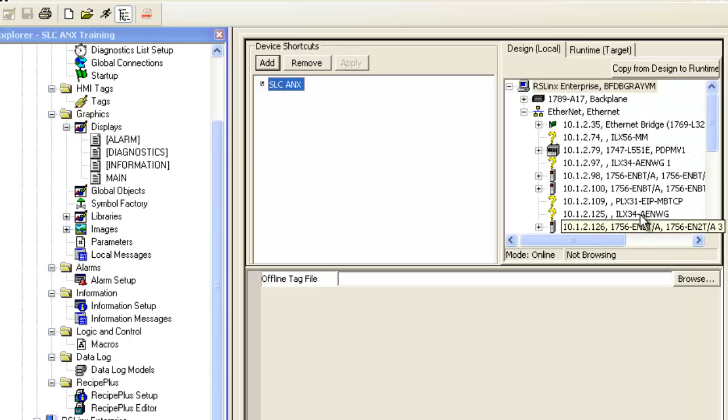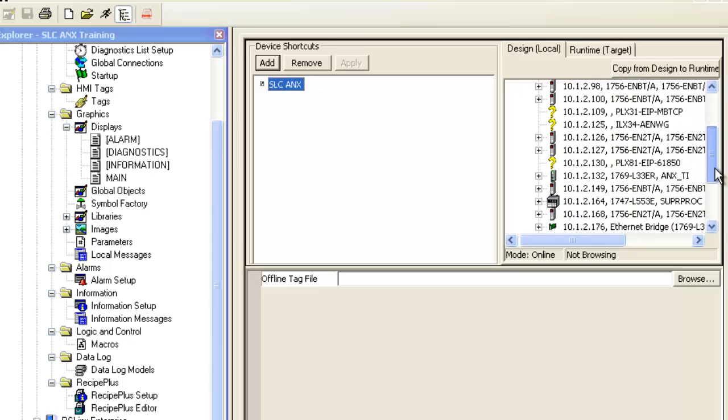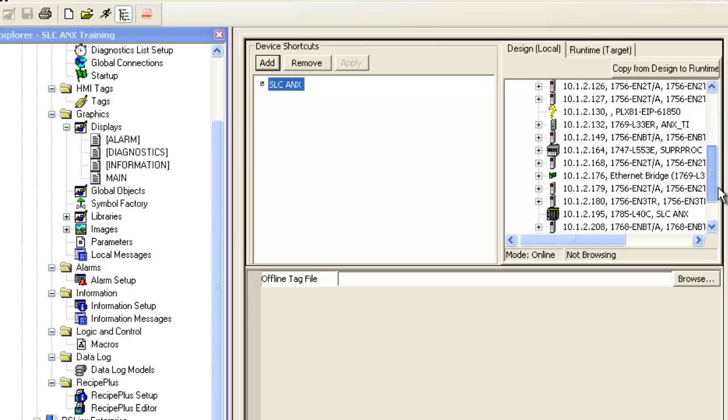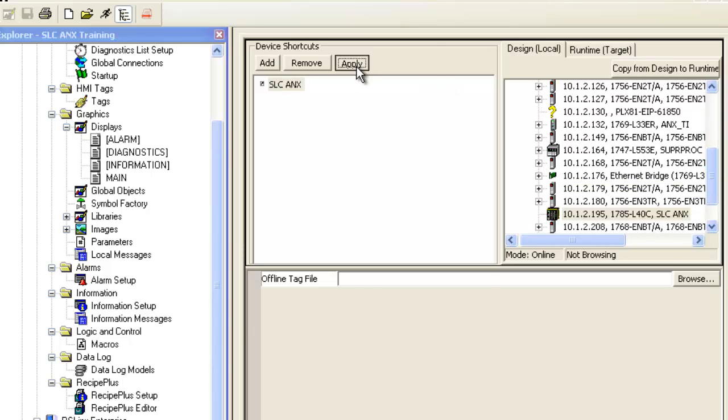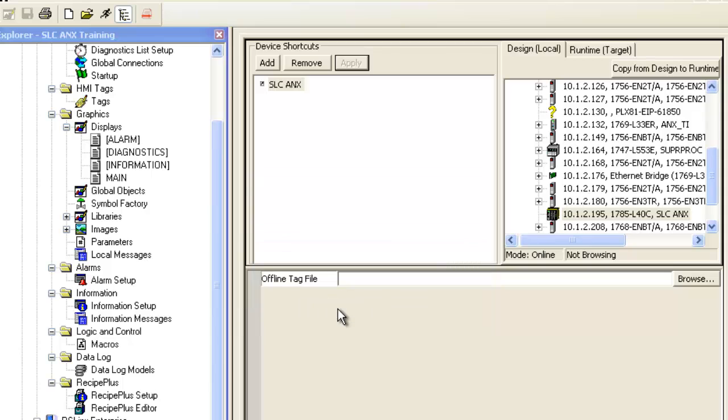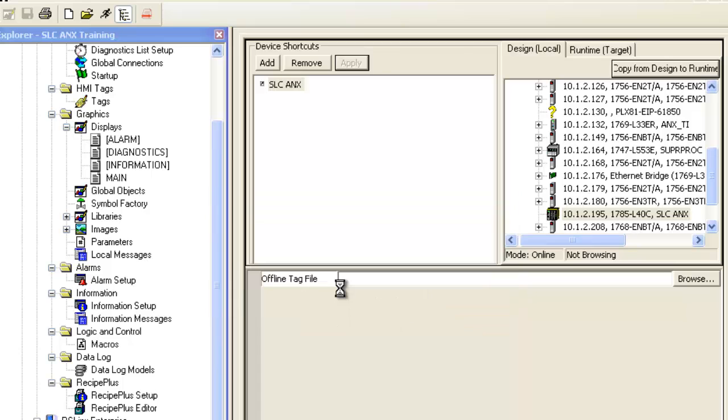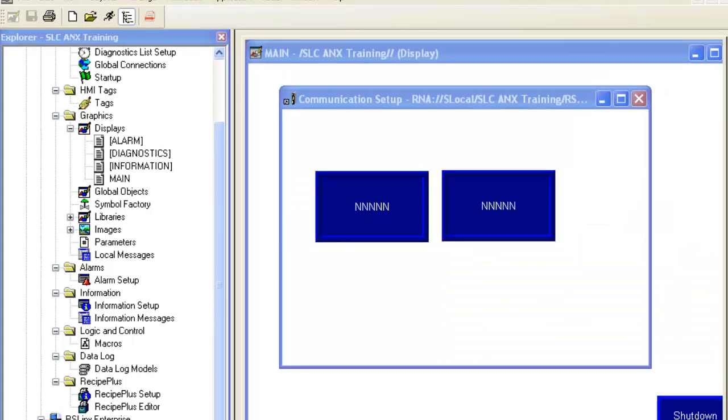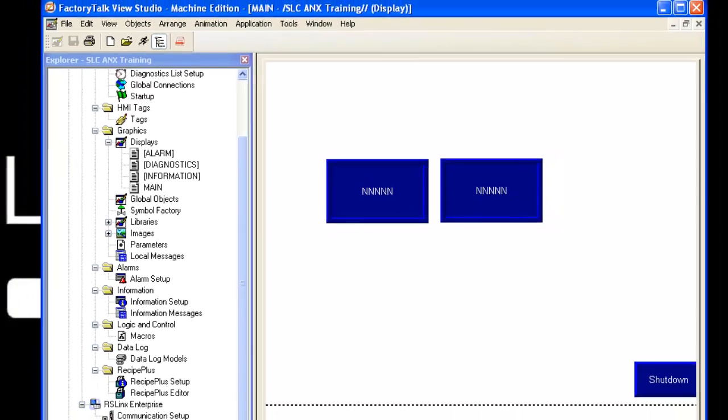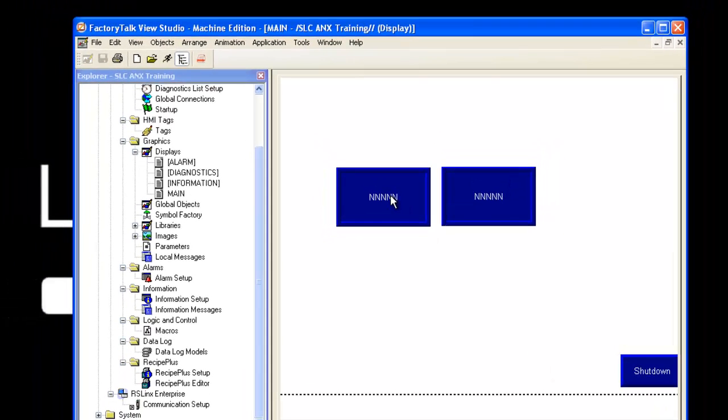The last thing we need to do here is click on the PLC5 40C and click Copy from Design to Runtime and then click OK. This will make the files in the SLC available over Ethernet. Next, we can assign the numeric displays a specific file number.